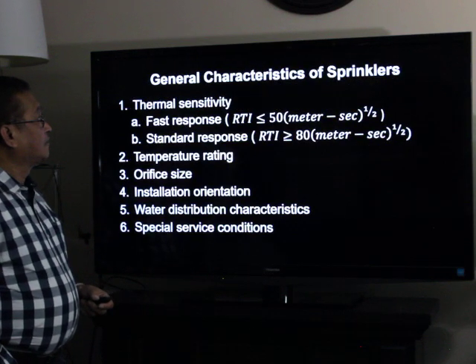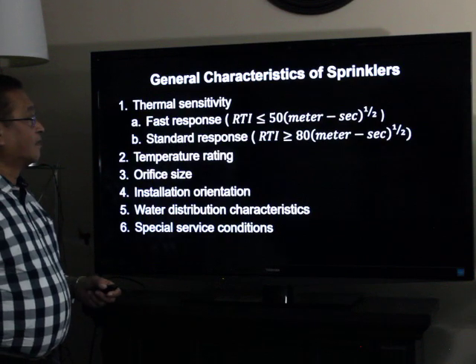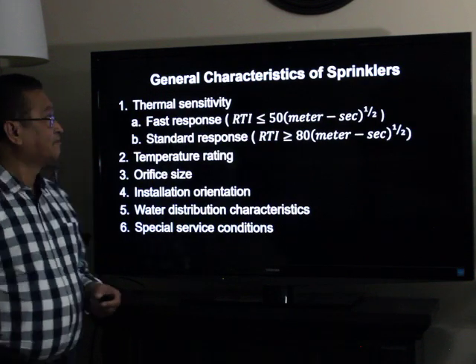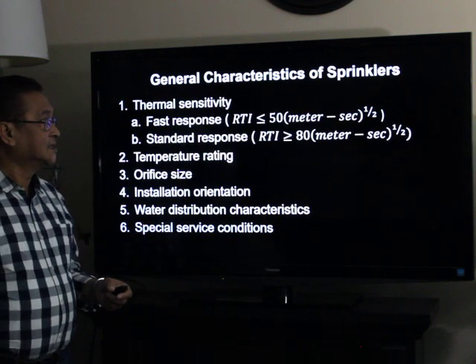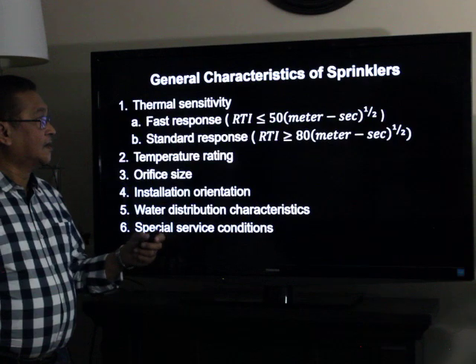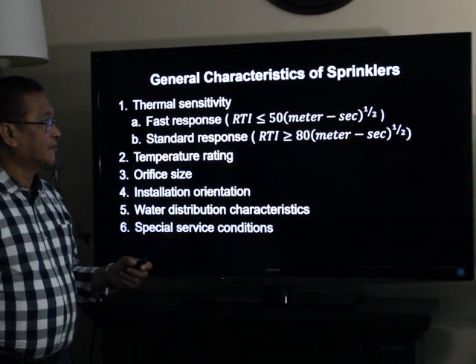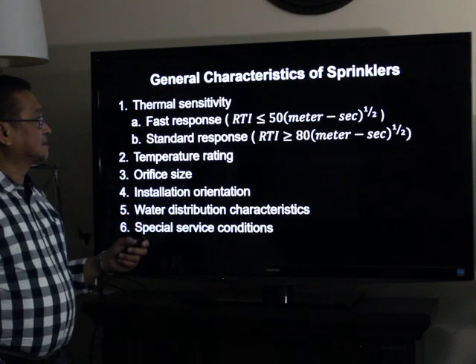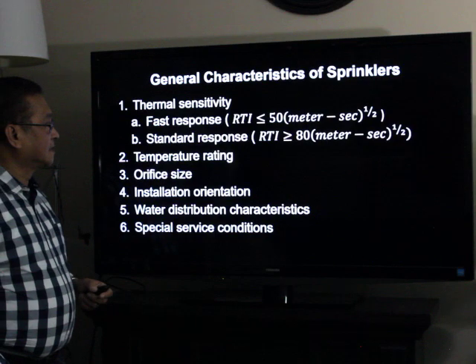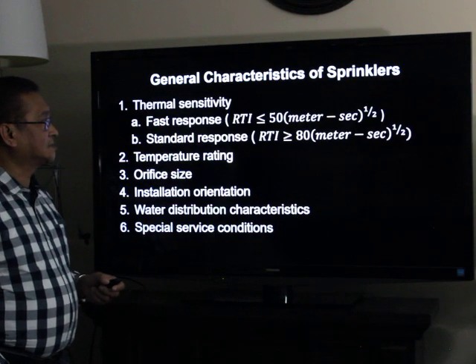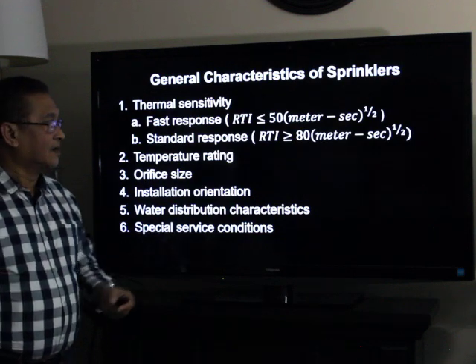General characteristics of sprinklers: number one is thermal sensitivity, with two classifications. The fast response has an RTI — Response Time Index — of 50 meter-second to the one-half or less. The standard response has an RTI of greater than or equal to 80 meter-second to the one-half.